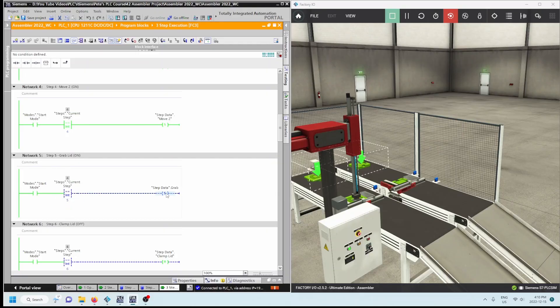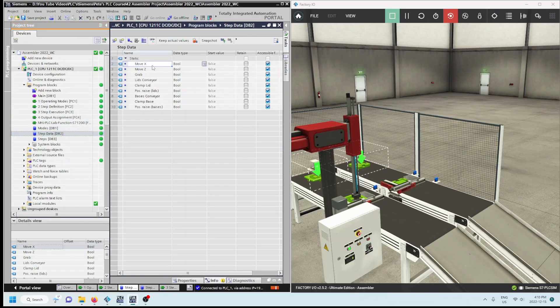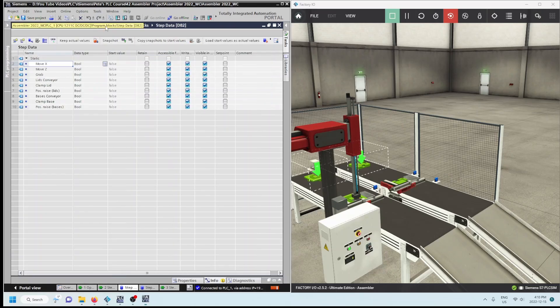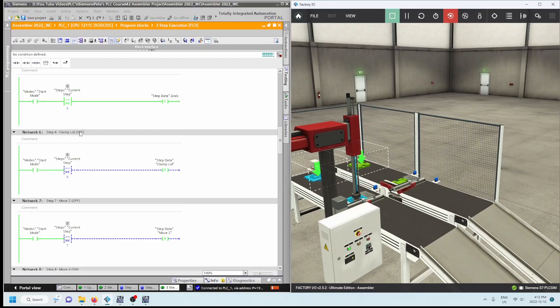Step five: I want to grab the lid. Once it gets to step five, set step data 'grab.' All these values are in our step data — move X, move Z, grab, lids conveyor — all available right here. We're basically setting these boolean values, and these boolean values will ultimately turn on our outputs. Within step execution we're not actually turning on outputs yet — all we're doing is setting bits within that data block. For step five we turn on the vacuum.